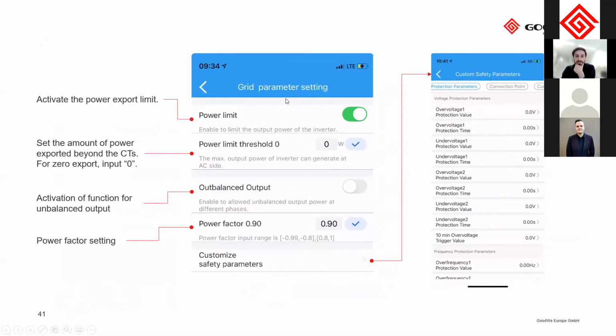Here on the power limit settings, you can activate the power limit here by checking this one, and you need to set the power limit threshold. If you want to have 0 export, you need to put a 0 here. Otherwise, if you want 100 watt, 1000 watt, 1 kilowatt, you enter it here. Make sure that this number here is in watt and not kilowatt or something like that. Unbalanced output is also a function for our hybrid inverter. Here you can select this one, and also here you also have options to change the power factor.